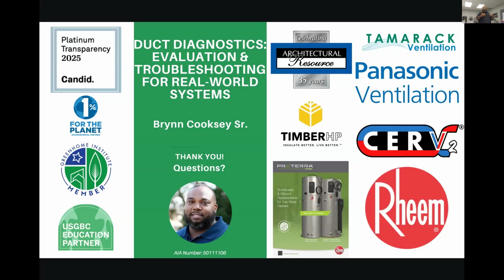The other test: if my airflow is pretty close, is it a shell problem? Am I leaking through the shell? Do I have poor insulation, where I maybe have a shell-related problem, too much load for the airflow that's coming out? So I have to look at that. Is it a duct leakage problem? So I have to look at that too. It just depends on what problem you're chasing, and that's why we cover those six different parameters.